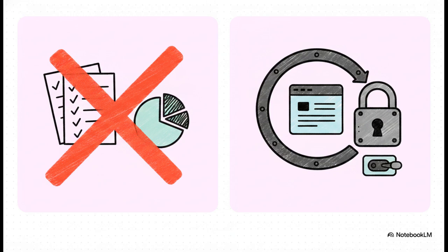Well, while you absolutely cannot use probability or code quality to drop your safety class, you can use verified external risk controls. Saying, "Hey, we've got 95% test coverage," is a totally invalid argument for lowering a class. But if you can point to an independent hardware interlock, or maybe a physically separate safety device that actively stops the hazardous situation, now we're talking. Those are valid class reducers, provided they sit entirely outside the software system itself and are rigorously verified.